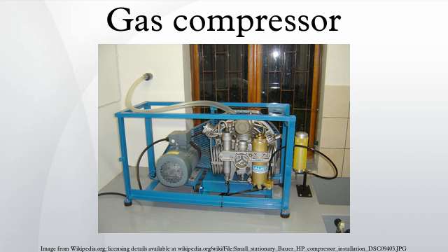Staged compression. In the case of centrifugal compressors, commercial designs currently do not exceed a compression ratio of more than 3.5 to 1 in any one stage. Since compression generates heat, the compressed gas is to be cooled between stages, making the compression less adiabatic and more isothermal. The interstage coolers typically result in some partial condensation that is removed in vapor-liquid separators.